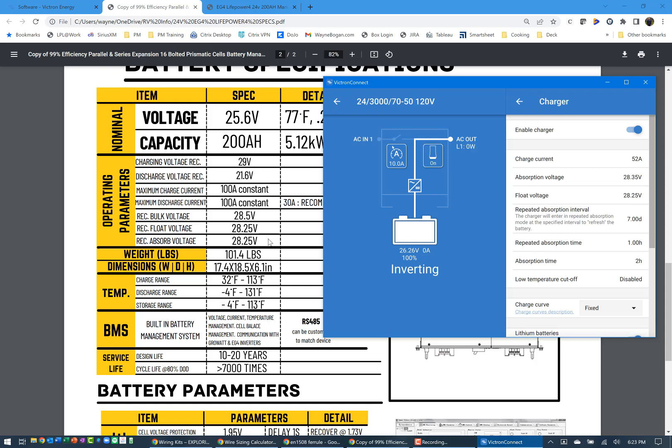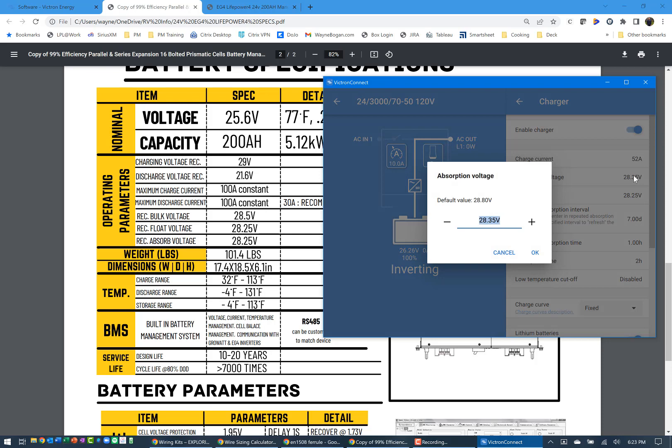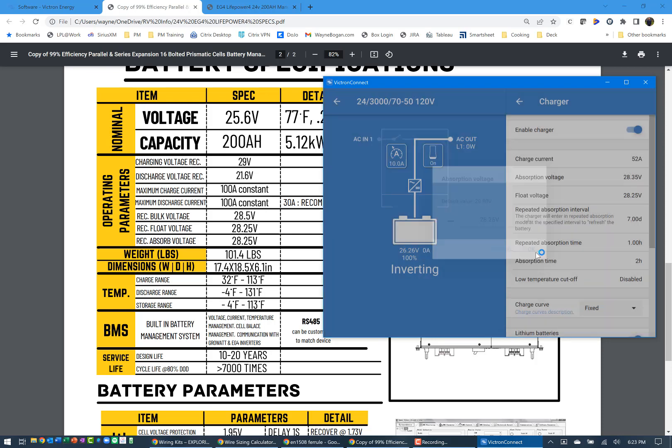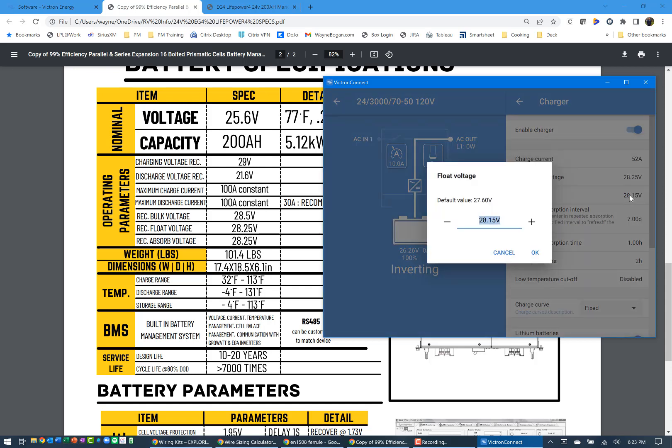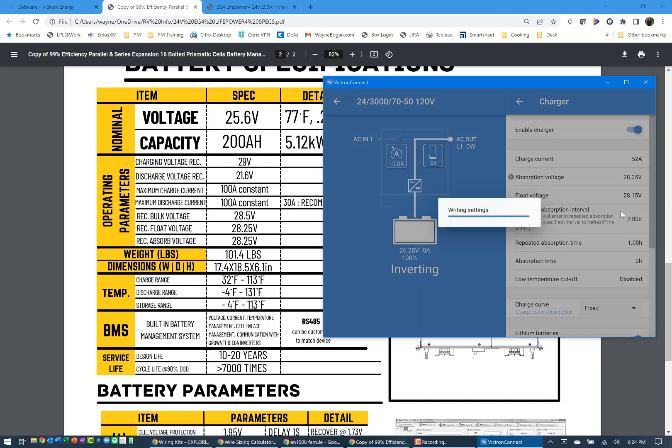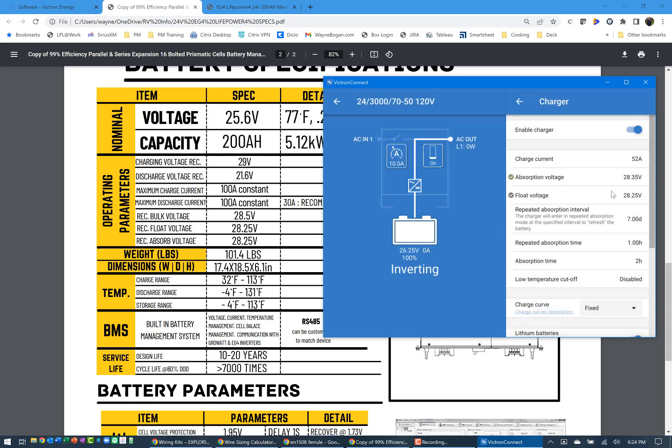So absorption should match the absorption of 28.25. Float is also recommended to be 28.25. So I've set both of those two, and you notice that the inverter, the MultiPlus comes back and actually changes these two. So I'm going to leave that as is based on what they're recommending with the float being at 28.25.